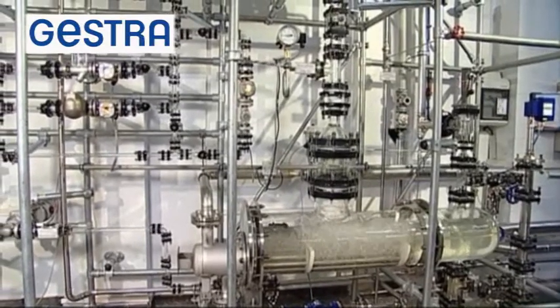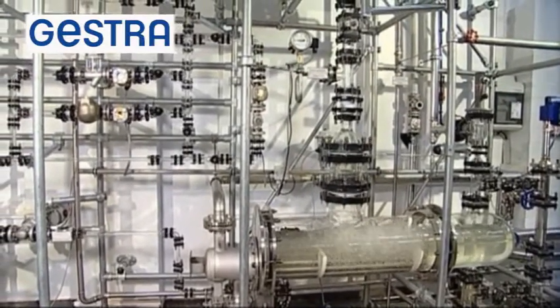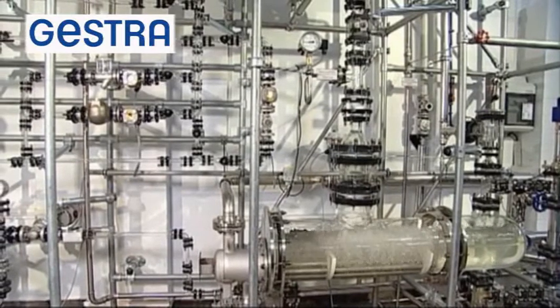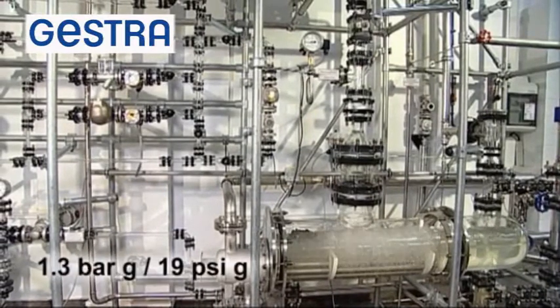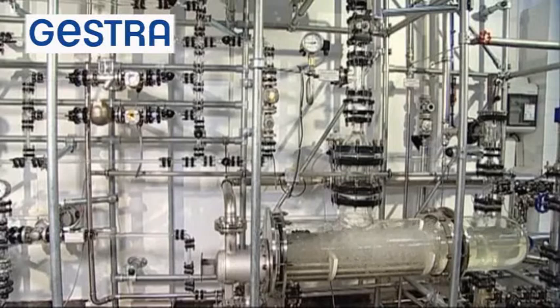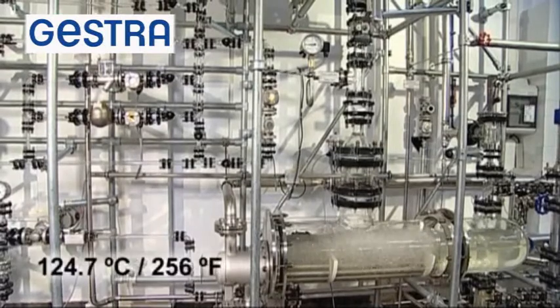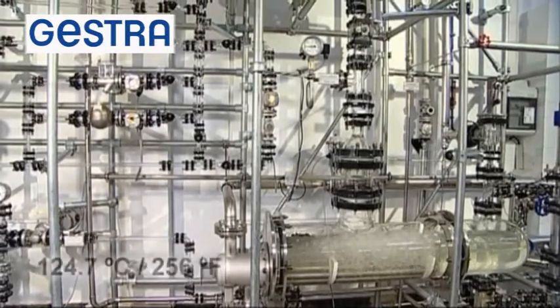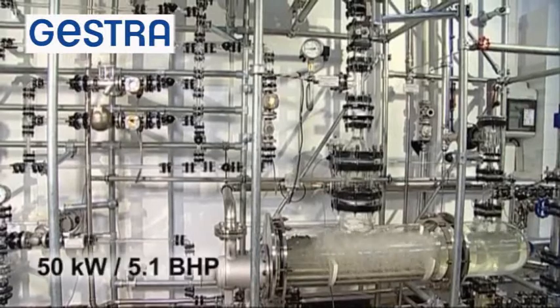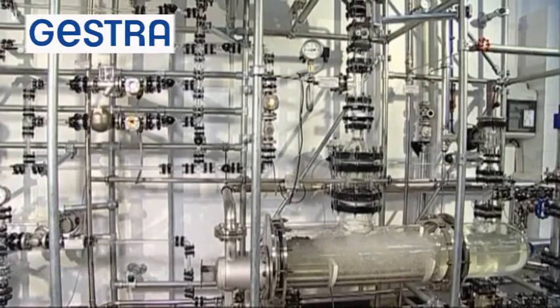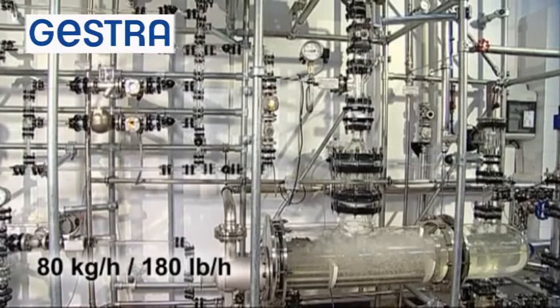Gestra AG, Bremen. The steam system consists of a secondary steam generator with a service pressure of 1.3 bar G, corresponding to a saturation temperature of 124.7 degrees centigrade. The capacity of the steam boiler is 50 kilowatts, which yields a steam flow rate of 80 kilograms per hour.